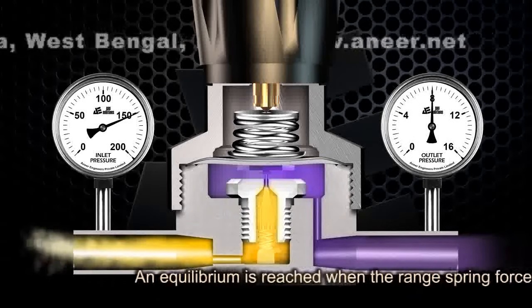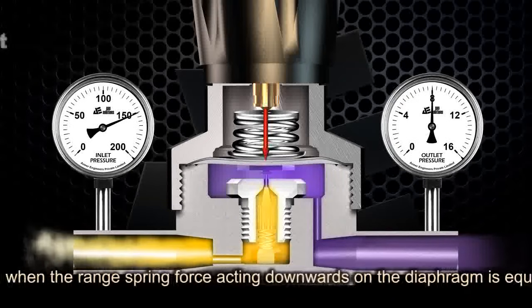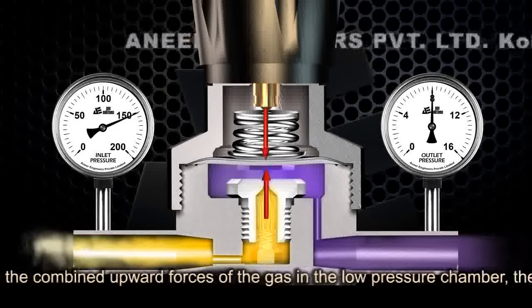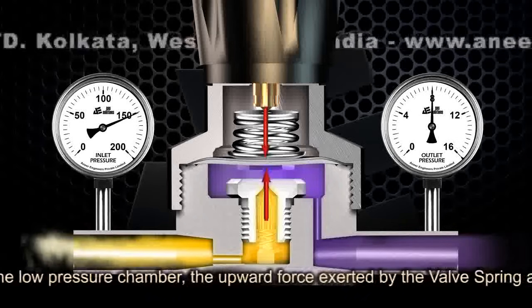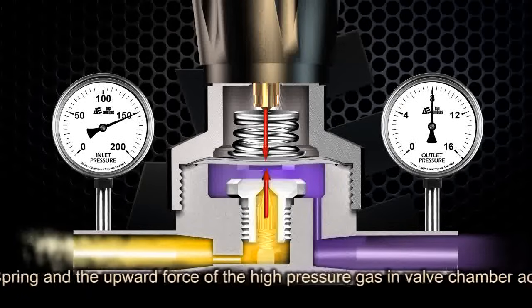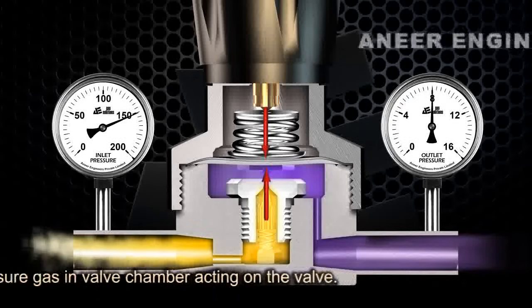An equilibrium is reached when the range spring force acting downwards on the diaphragm is equal to the combined upward forces of the gas in the low pressure chamber, the upward force exerted by the valve spring, and the upward force of the high pressure gas in the valve chamber acting on the valve.